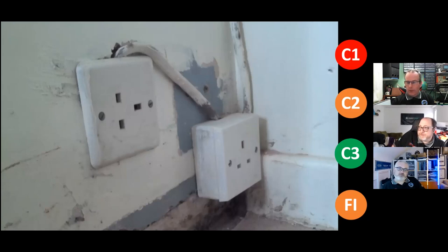Yeah, I mean, there's nothing obviously dangerous for what you can see. The cables are there. They're not exposed live parts or anything. And it could be a spur off of a spur, but depending on the actual loads that you plug in, that might not be a problem. I think the biggest thing for me is the way the cabling has been lashed in. It's just no due care and consideration for mechanical protection of it. And straight away, I've always said, strain placed upon conductors is a key thing.